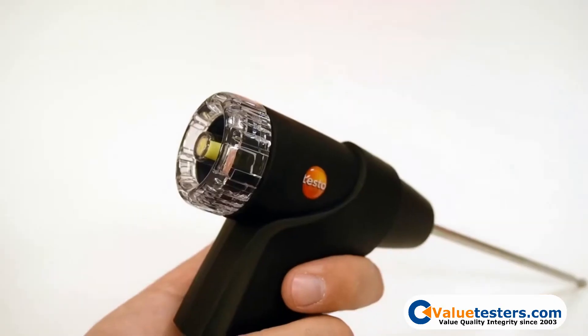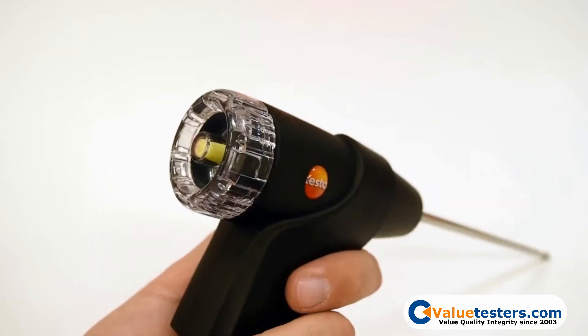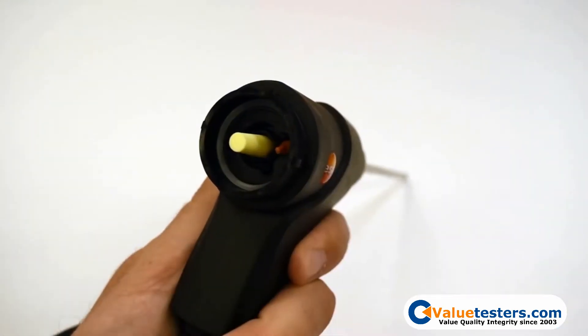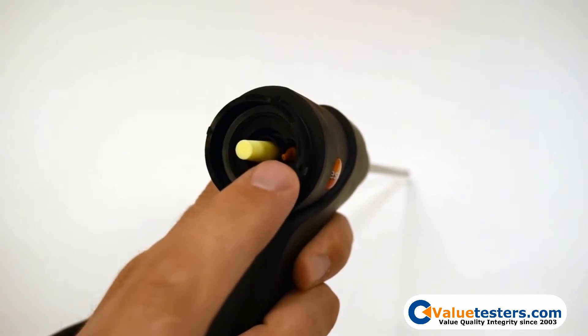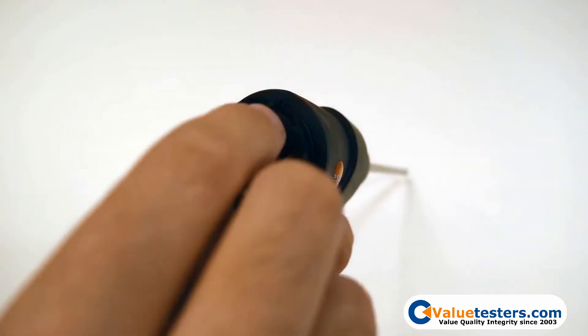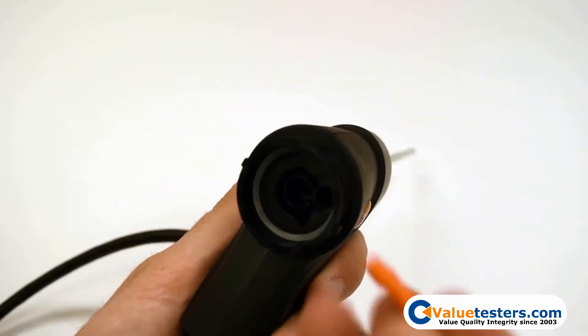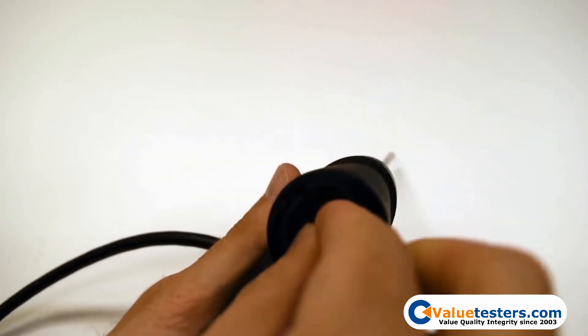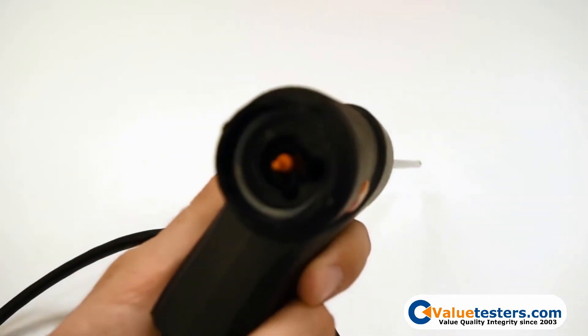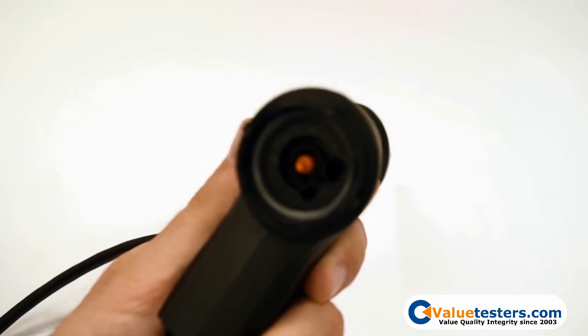To access the filter, rotate the plastic cover counterclockwise to unlock. You will find the orange plug stored conveniently in the space provided in the back of the probe handle. Remove the yellow cone filter and replace it with the orange plug. You can then put the plastic cap back on the probe handle and rotate clockwise to lock it back in place.